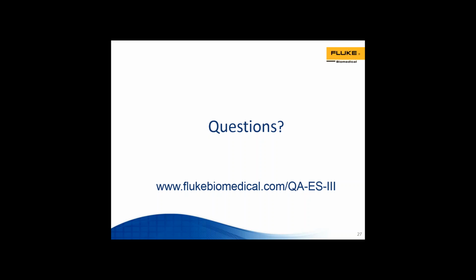And so 1 year right now is what we are highly confident or highly certain about. And by us providing that level of certainty about our accuracy and keeping that accuracy over the duration of the calibration cycle, that's why we say 1 year. If we thought we could extend it and you would always get the experience of a longer period than that, we would specify a longer period. So 1 year is our current calibration cycle, especially including QA-ES3. And we recommend that you always send your test equipment back to its original manufacturer or their authorized service center, because you will get the best results out of your calibration, and any hardware or firmware updates that need to have been included prior to any adjustment that's made, should an adjustment be required.